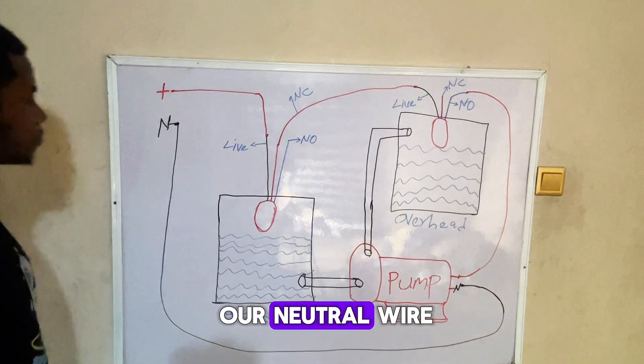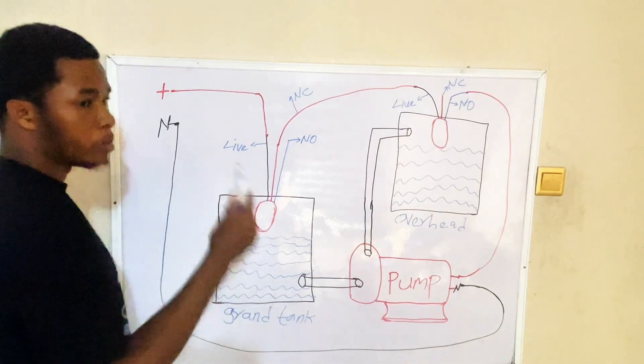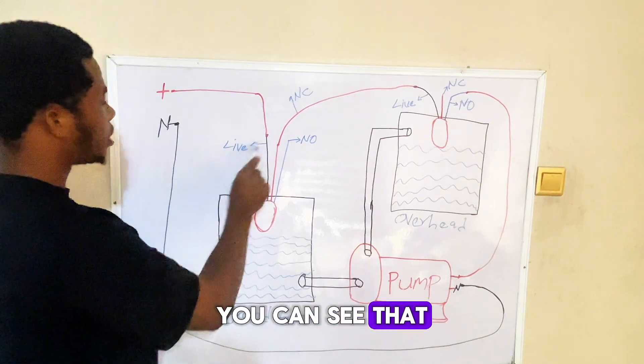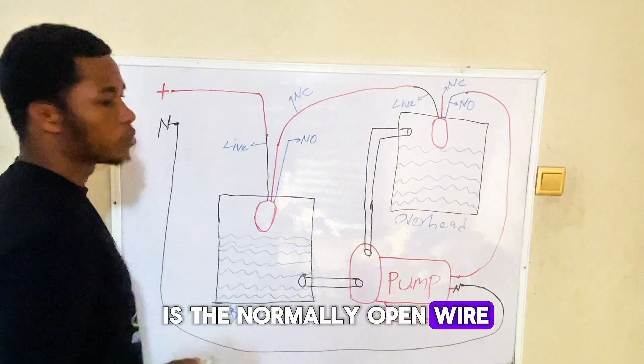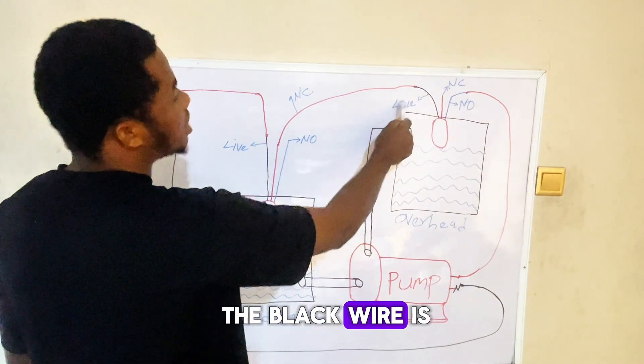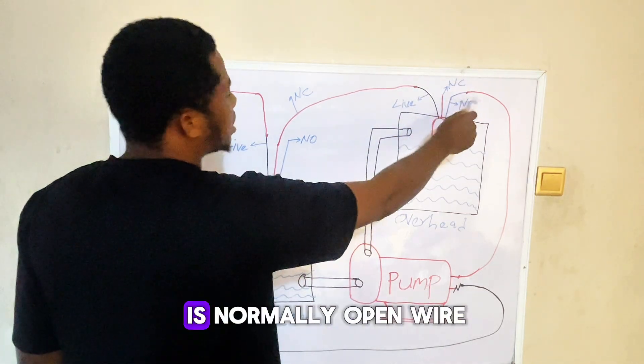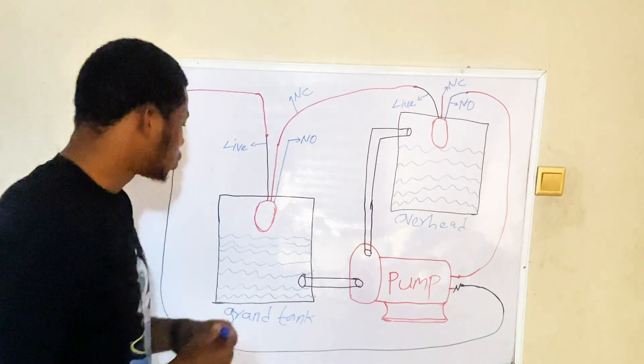This is our live wire and this is our neutral wire. Remember, every float switch has three wires. The black wire is the live wire of the float switch, the red wire is the normally closed wire, and the blue wire is the normally open wire. Our second float switch has the same configuration — black is live, red is normally closed, and blue is normally open.